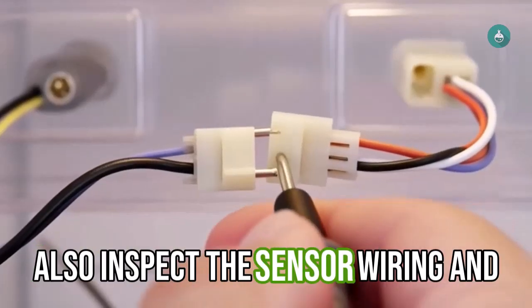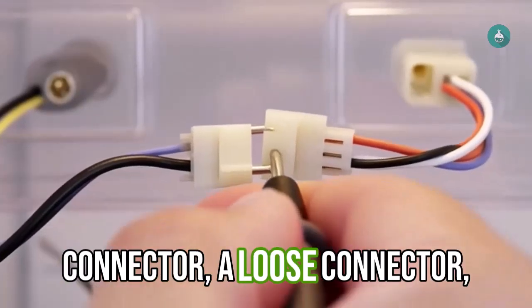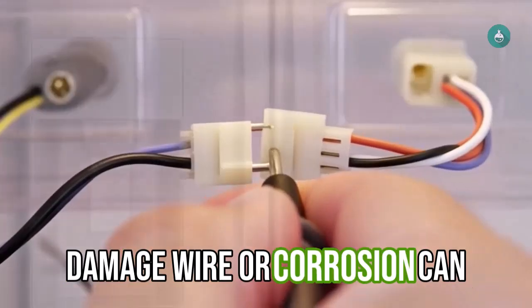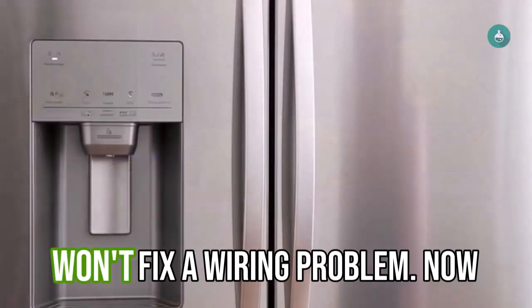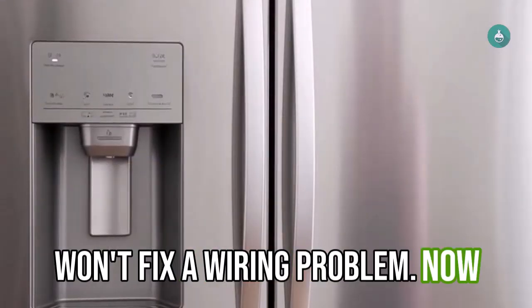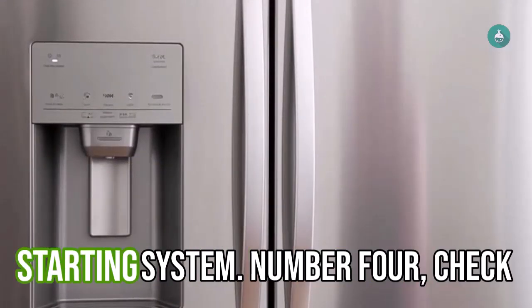Also inspect the sensor wiring and connector. A loose connector, damaged wire, or corrosion can create symptoms similar to a bad sensor. This is an important point because replacing a good sensor won't fix a wiring problem. Now, let's move to the compressor starting system.